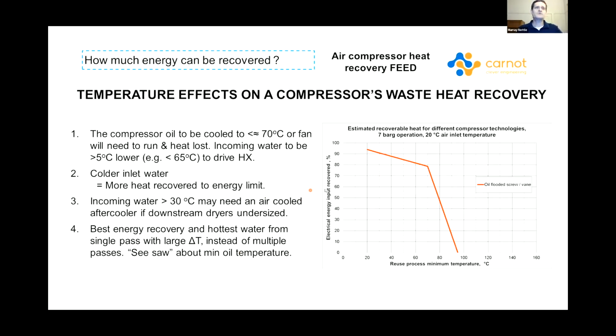The important thing is that the colder the water coming in, the more heat you can recover. If your water coming in is too hot, you won't cool your air down enough. So your dryer and downstream equipment might be undersized, so you need to be aware of that. And for the best energy recovery, you need to go for a single pass of the water. So you need to get as big a temperature rise in that water as you can. What I mean by that is to have that 70 degrees in the water, if you've got, say, a 5-degree approach temperature in your coolers, the water coming in needs to be at 65 degrees.